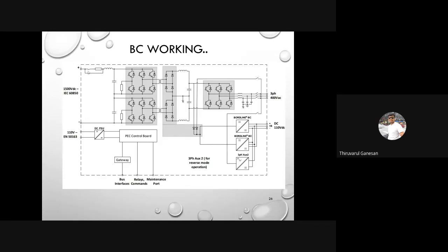Here it is a pre-charge system, and the inductor will be decided based on your DC link capacitor and the complete charging circuit, like an RLC circuit. It will depend on your inverter capacitor, the DC link capacitor value. Also, it depends on your voltage, your converter current rating, the ripple rating and THD value, and it will be decided.